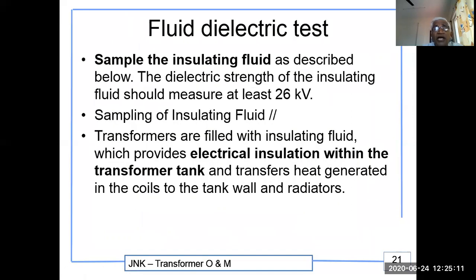Fluid dielectric test. Sample the insulating fluid as described below. The dielectric strength of the insulating fluid should measure at least 26 kV. Sampling of insulating fluid can be done. Transformers are filled with insulating fluid, which provides electrical insulation within the transformer tank and transfers the heat generated in the coils to the tank wall and the radiators.